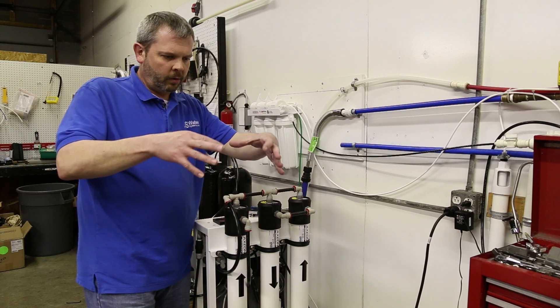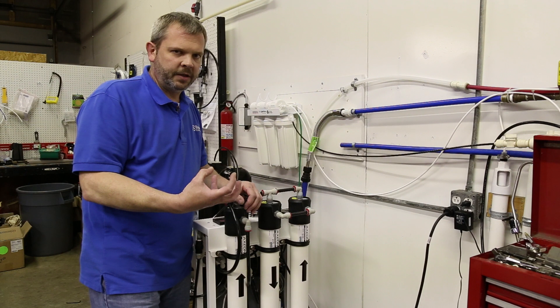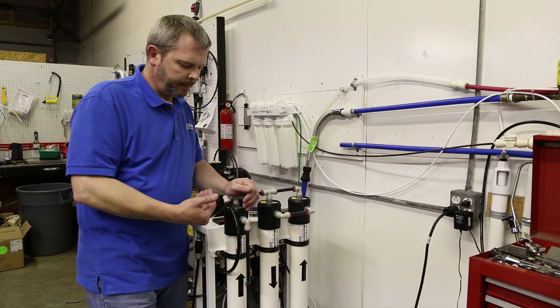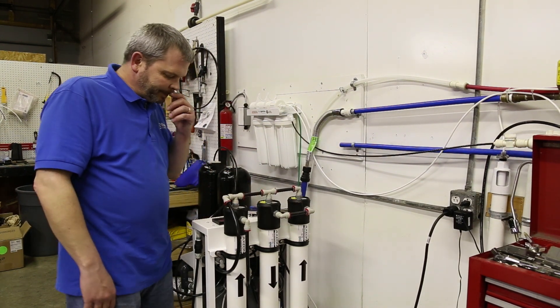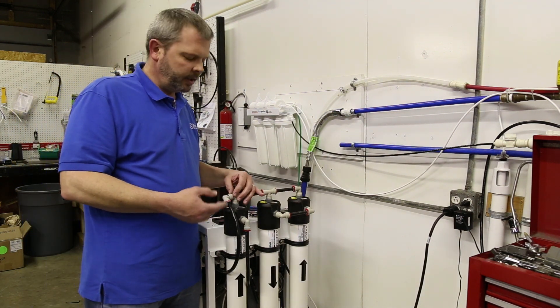There's something called a skirt seal that literally looks like a woman's skirt that comes off the side of the membrane. That particular seal is what seals off the bad water and forces that bad water in through the membrane. We're going to take a membrane out and I can show that to you.